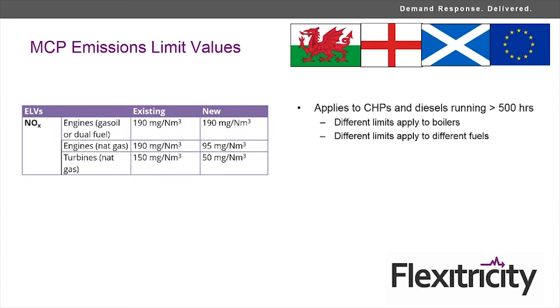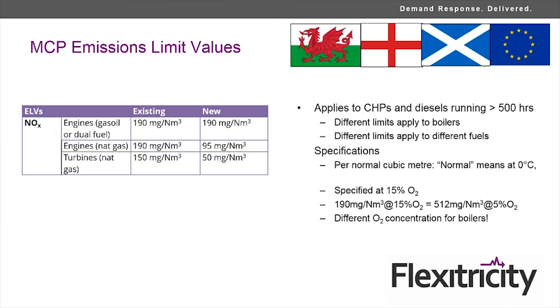Now, to understand that 190 milligrams per normal meter cubed, it's very important to look into the detail of what that means. A normal meter cubed is a cubic meter of engine exhaust gas that has cooled to 0 degrees C, reached atmospheric pressure, and been mixed down with air so that it has an oxygen concentration of 15%. This is a way of standardizing the measurement so that we're all measuring the same thing. But it does mean that when you read the numbers, you need to make sure you're comparing like with like. Generally speaking, the word normal doesn't change, but the percentage of oxygen does.